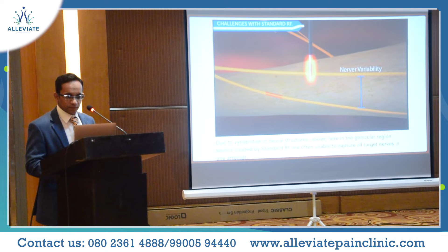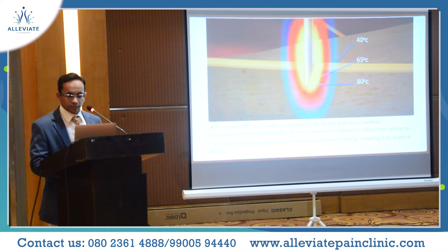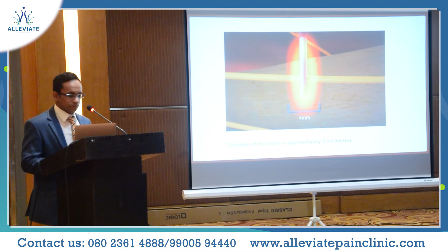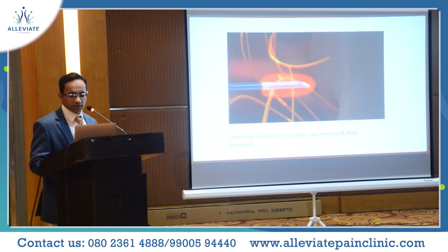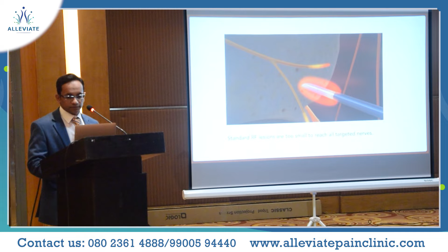With standard RF, ionic heating is greatest at the probe and tissue interface, around 80 degrees. Since lesioning occurs only within the area immediately adjacent to the probe's active tip, the lesion projects distally a minimal distance beyond the tip, resulting in an elliptical shape, or a candle flame lesion. The diameter of the lesion is approximately 4 millimeters. Therefore, because of its shape, size, and lack of distal projection, standard RF lesions are too small to reach all the targeted nerves. This is a comparison between the standard RF and the cooled RF. We can see here the volume is smaller, there is minimal distal projection and no angle independence.